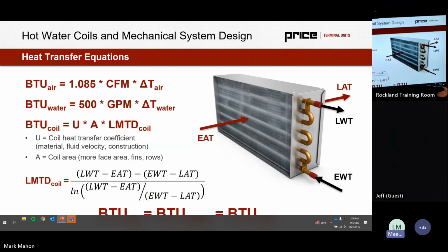The reason this happens is that there's actually a third equation, which is the coil capacity, which is dependent on the log mean temperature differential through the coil, a complicated equation that just tells us the average difference in temperature between my water side and my air side for the totality of the coil. Log mean temperature differential is also the rationale for why we want counterflow heat exchangers, not parallel flow heat exchangers. I know that was a fluids lab that I did during my engineering degree. I'm sure somebody else in the room has had similar experience.